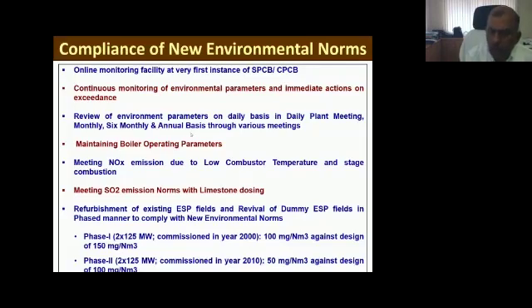Then, as already explained, NOx emission is being maintained because of the low combustion temperature zone. The boiler combustor temperature is always almost in the 750 to 800, 850 range, and this supports the reduction in NOx. So this is a very important and critical parameter for us and is being monitored regularly by the operation people, and on the parameter side also through the online SPCB, GPCB and CPCB websites.